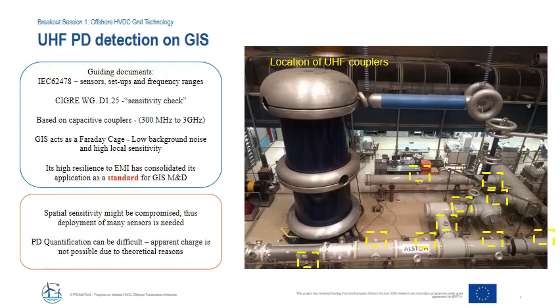But also they are used to understand the dielectric properties of alternative gases that will soon replace SF6, especially in future DC GIS applications. Conventionally, PD measurements on GIS have relied on several broadband techniques to detect the electromagnetic waves produced by a PD event, for example, using capacitive couplers. For this, standards such as the IEC 62478 advise on the setups and working frequency ranges, while other documents, such as the CIGRE Working Group D1.25, define a sensitivity check procedure to verify that a UHF measuring system in the field can pick up signals equivalent to 5 picocoulombs as measured by the conventional standard IEC method during laboratory tests.